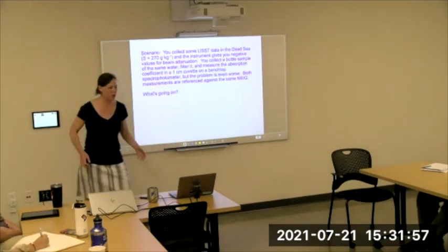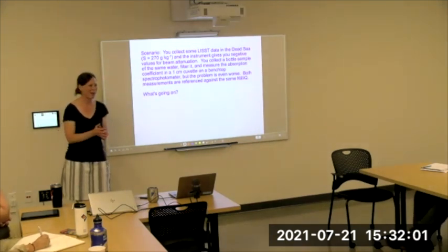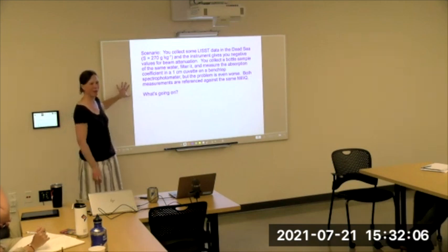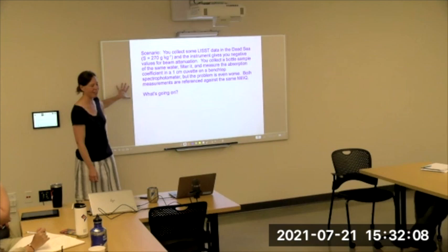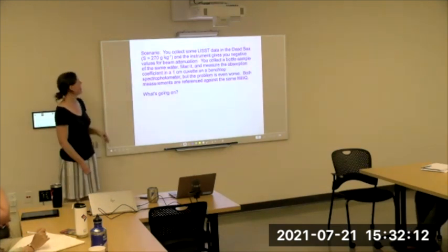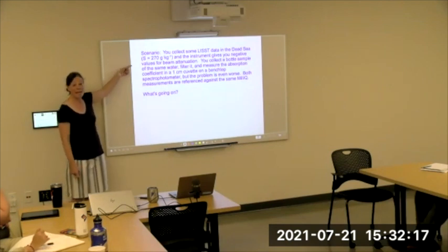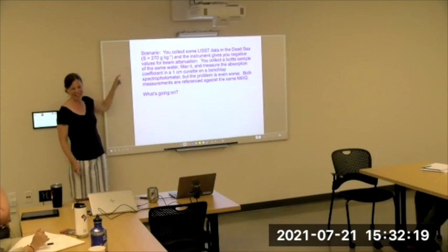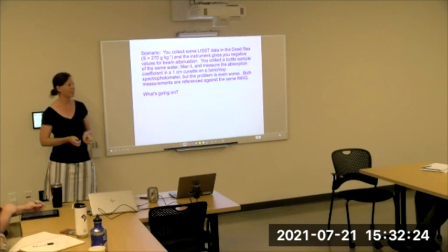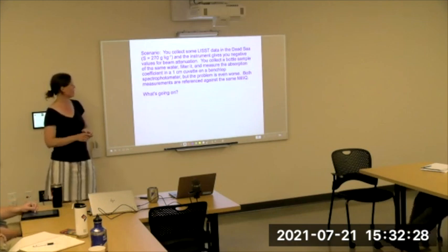Okay, so this relates a little bit back to some of your presentation this morning, thinking about absorption measurements in your spectrophotometer. Here's a scenario, and it's a bummer that Emmanuel's not in the room because this is actually his scenario. Well, I wrote it up, but he experienced this. If you collect some data in the Dead Sea, which has massive salinity, super saturated, 270 grams per kilogram of salt, and the instrument gives you negative values for beam attenuation.